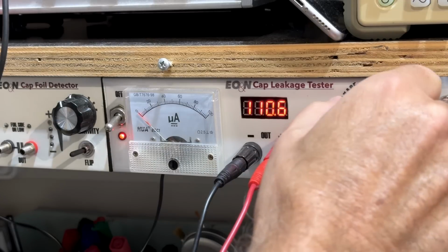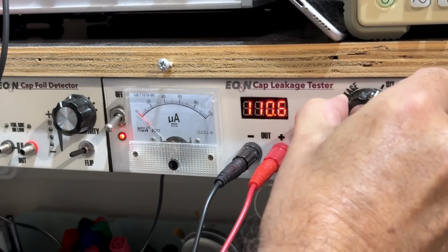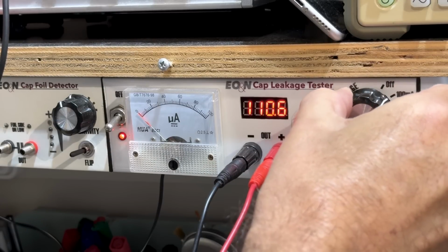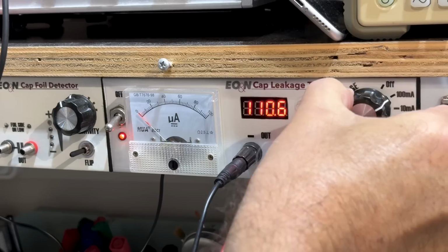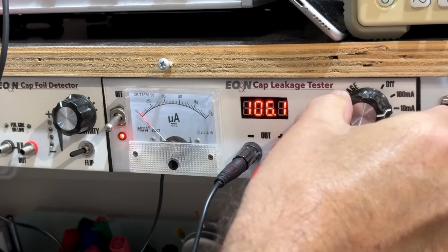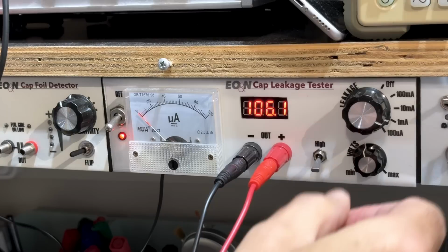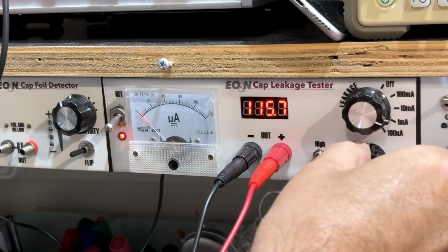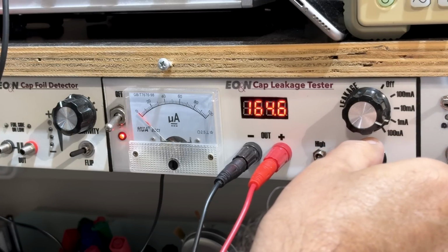I've got this at zero current, 100 milliamp range, and I see no flicker. I'm going to the 10 milliamp range, still no flicker of current. 1 milliamp range, still no flicker of current. Let's step this up to the limit.